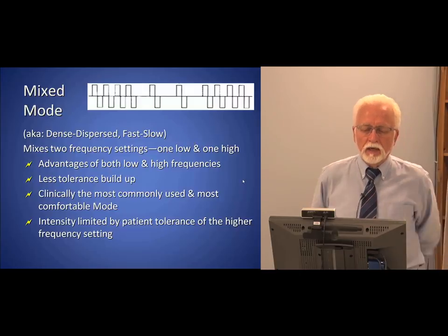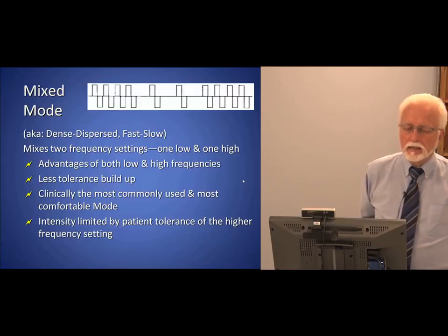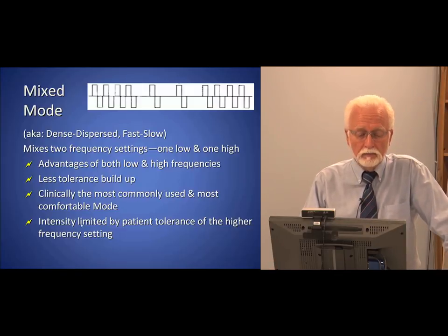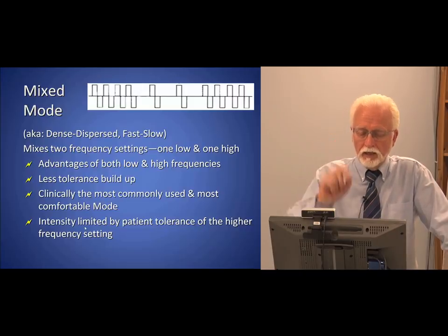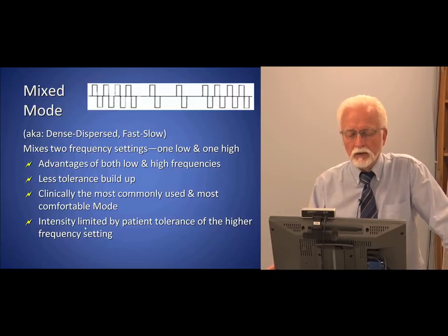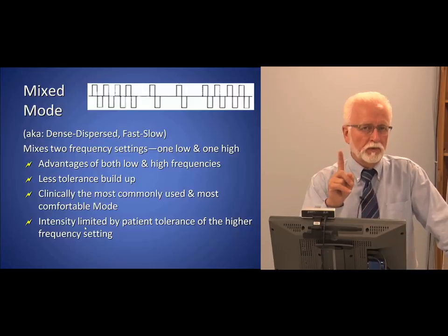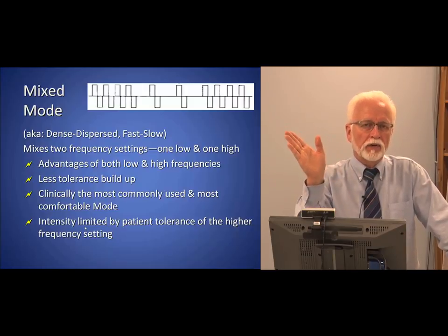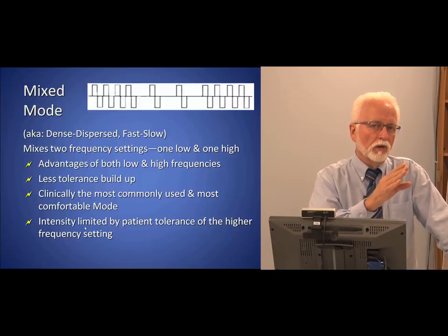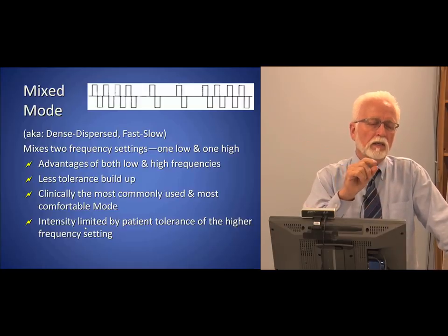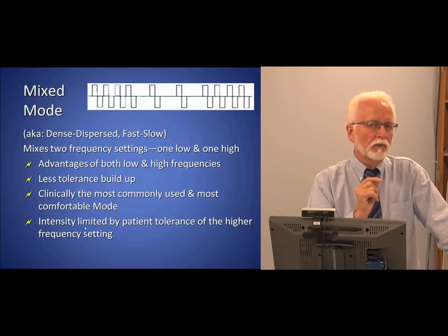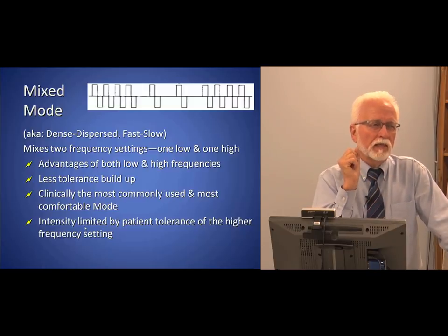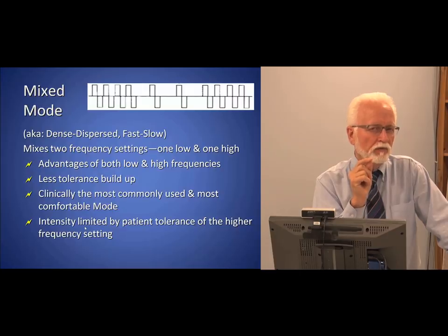Less tolerance buildup, and the intensity can be limited, and this is the caution of this mode. The intensity that you turn it up is limited by the patient's tolerance of the higher of the two frequency settings. Because typically, if it's set at 2 hertz and 100 hertz, at 2 hertz, it's going to be pretty comfortable. It's going to be just a little tapping.